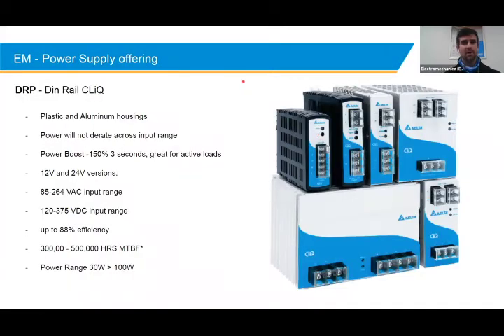Looking at the little bit more advanced series, we're going into the CLIQ range. We offer the CLIQ 1 and the CLIQ 2. So let's have a look at the CLIQ 1. Plastic and aluminium housings. This power supply does not derate its wattage across its entire AC input range. Often some power supplies, if you're only giving it 90 volts AC, you won't get its full wattage out. But in the DRP range, that's not the case. You've got full power range across the entire AC input spectrum.